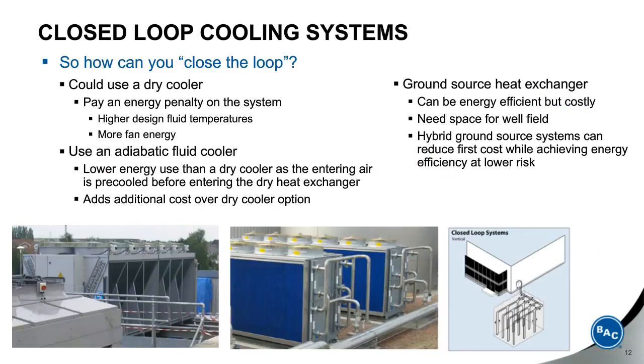You could use a dry cooler, but you pay an energy penalty on the system through higher design fluid temperatures. If you remember the Baltimore design day that I mentioned earlier with the 95-degree dry bulb, you would be lucky to get 105 or 110 degrees off the dry cooler during that design day, which would then be an energy penalty on the system. And remember now, the heat rejection is often the lowest energy part of the system.